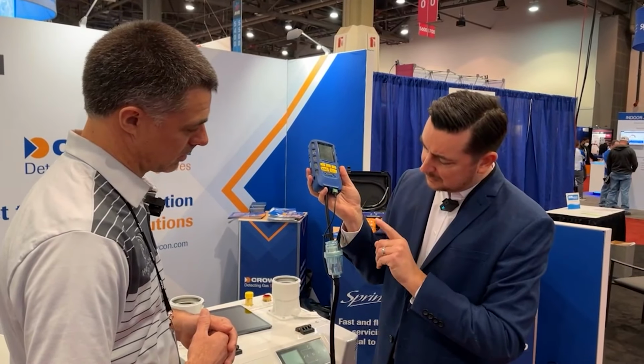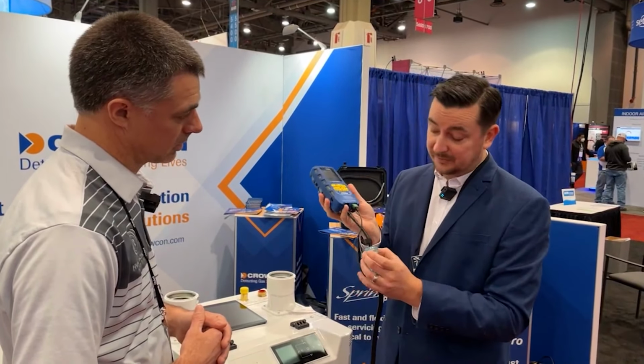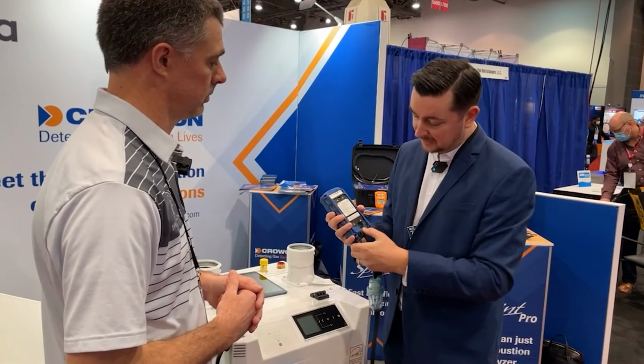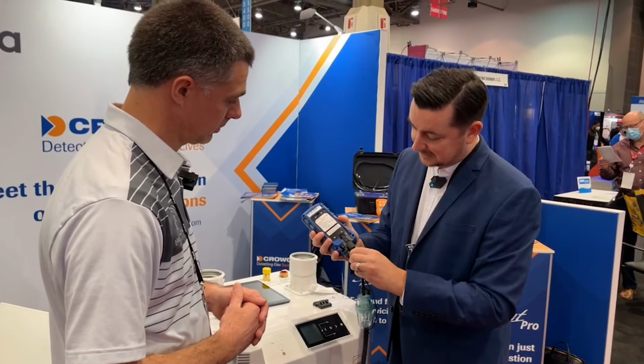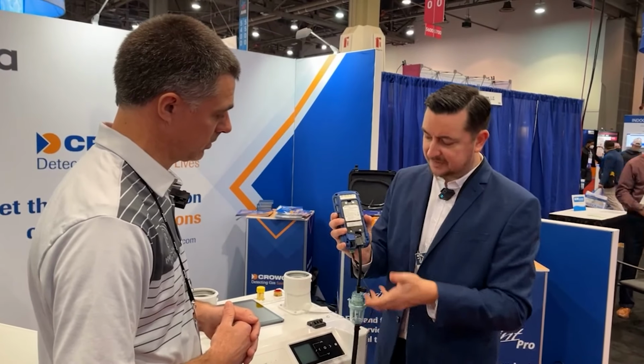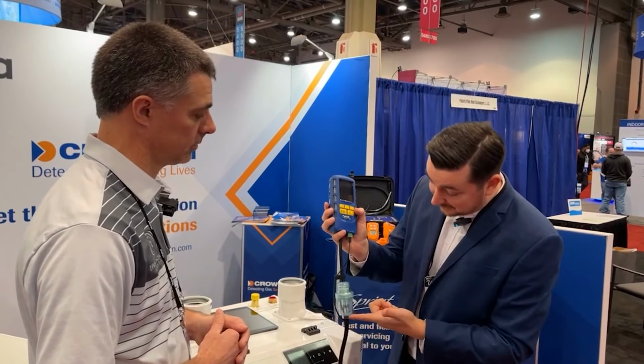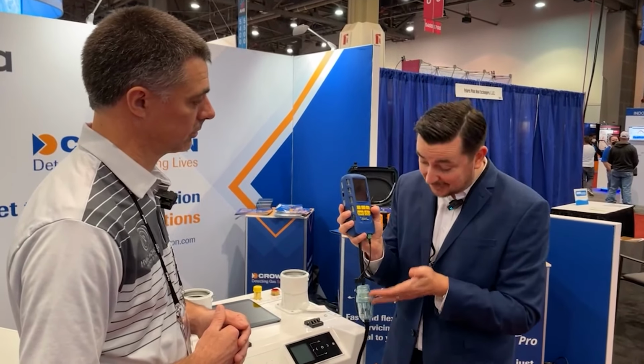You've got a dust filter in there. You've got a 3-micron filter in there as well, so that's a specific hydrophobic filter that's tailored to not let water through. It's a 3-micron, so really fine holes that allow the gas to flow but not the water. And then at the point where it joins the device, our positive click connector, you've got an extra filter as well. So there's 3 stages of filtration, and we've got intelligent algorithms that detect the flow rate of the pump. So if this does fill with water, you don't notice, you don't empty it, and it eventually overcomes the filters, the device will detect a change in flow rate and shut off the pump. It'll beep up a bright orange warning on the screen saying, blockage detected, check your water trap and filters.